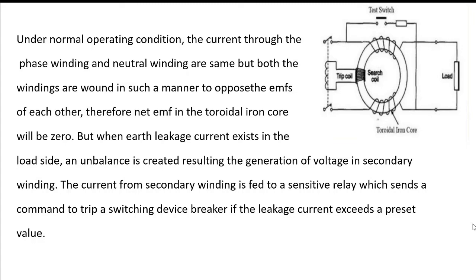Under normal operating conditions, the current through the phase winding and neutral winding are the same, but both the windings are wound in such a manner as to oppose the EMFs of each other. Therefore, the net EMF in the toroidal iron core will be zero. But when earth leakage current exists in the load side, an unbalance is created, resulting in the generation of voltage in the secondary winding. The current from the secondary winding is fed to a sensitive relay which sends a command to trip a switching device breaker if the leakage current exceeds a preset value. This is about current ELCB.